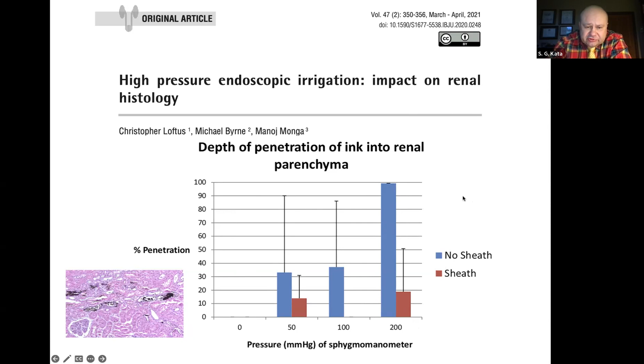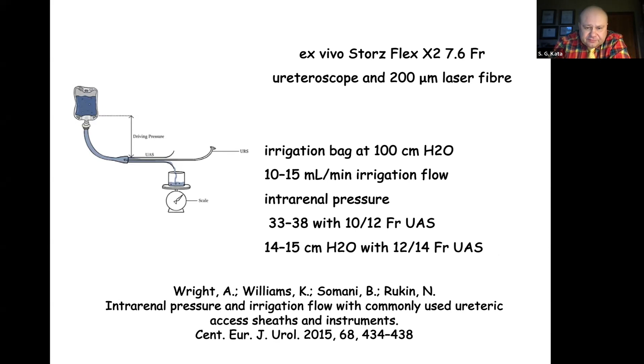Another study tried to see different sizes of access sheath and their impact on pressure within the kidney. They used a standard Storz fiber optic ureteroscope and a 200 micrometer laser fiber. The irrigation bag was at a level of 100 centimeters of water column, so they got irrigation of around 10 to 15 milliliters per minute. Intrarenal pressure was much higher for the smaller access sheath with an inner diameter of 10 and outer diameter of 12, compared with the 12 and 14 access sheath. And you can see 14, 15 is acceptable pressure, bearing in mind the previous study I told you about, on pressures and damage to renal parenchyma.